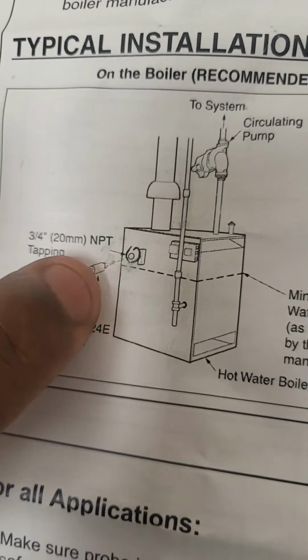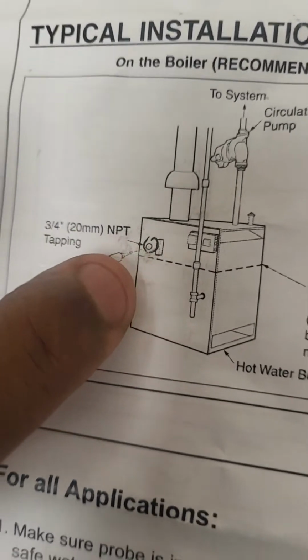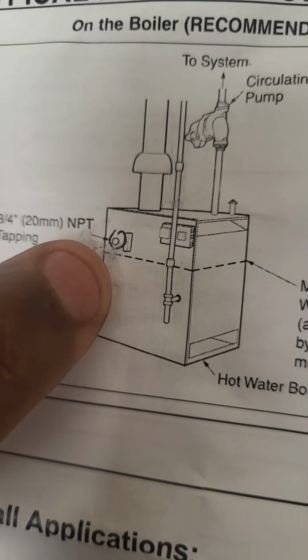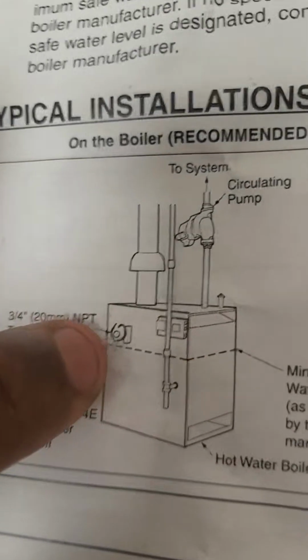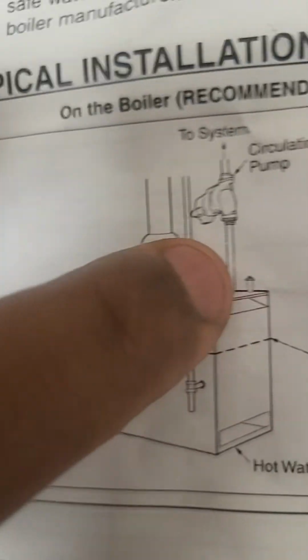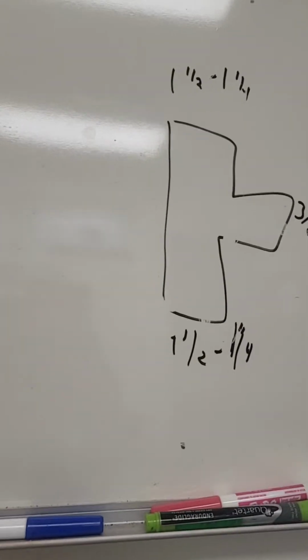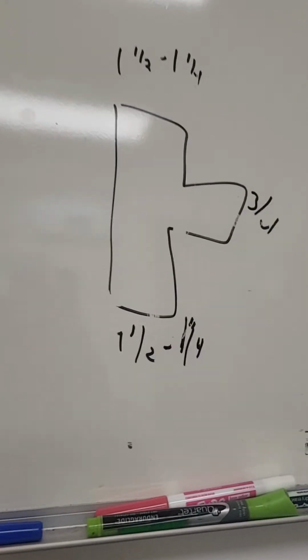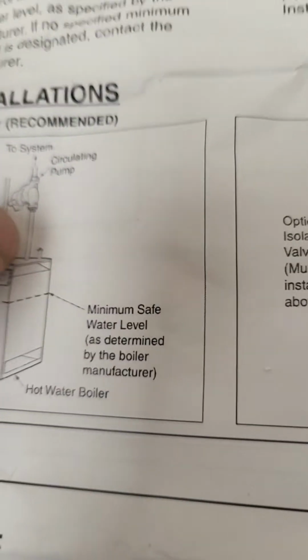When installing a low water cutoff that wasn't there before, you can put it in on either the left or right side of the 3/4 inch taps on the side of the boiler, or use a 1.5 inch or 1.25 inch by 3/4 inch black T. This is going to take some craftsmanship.